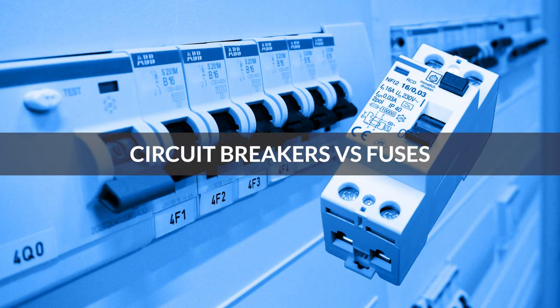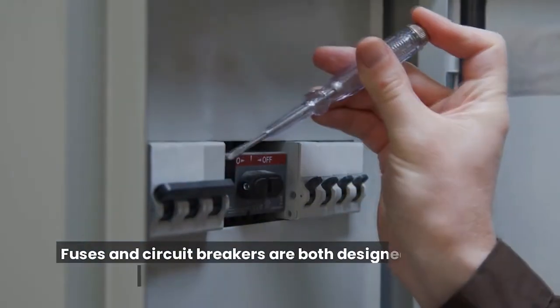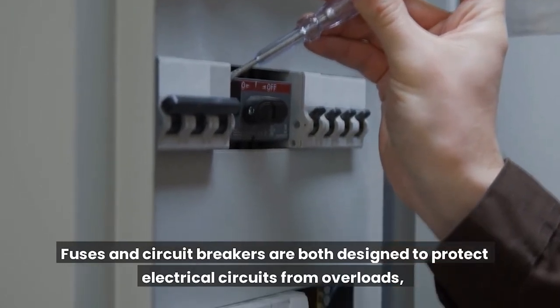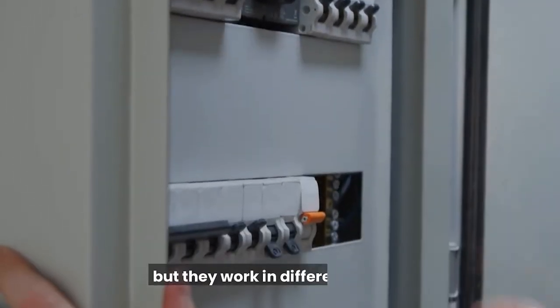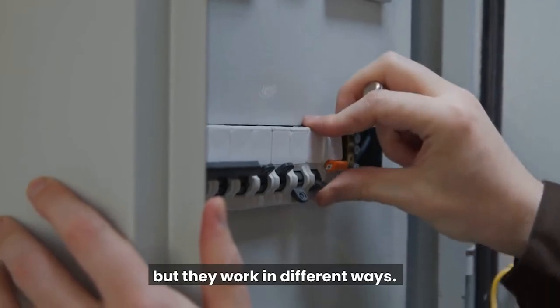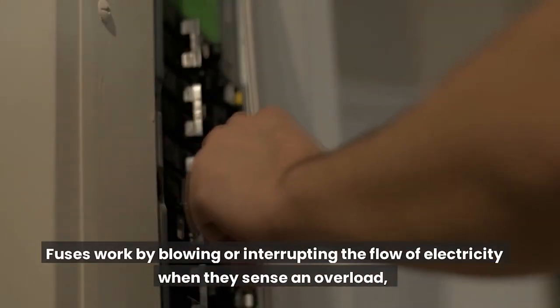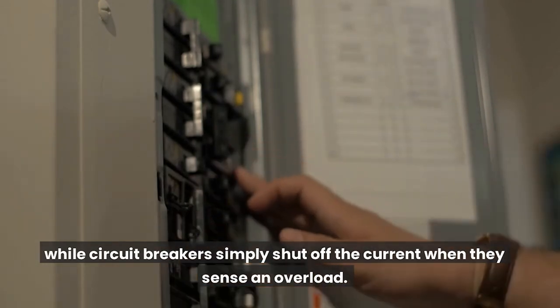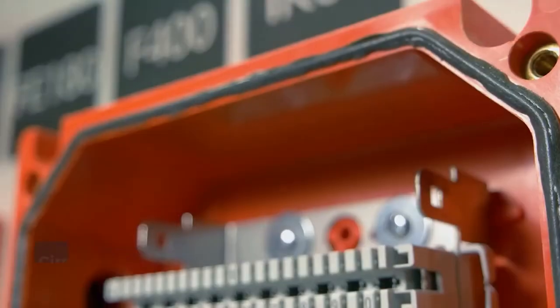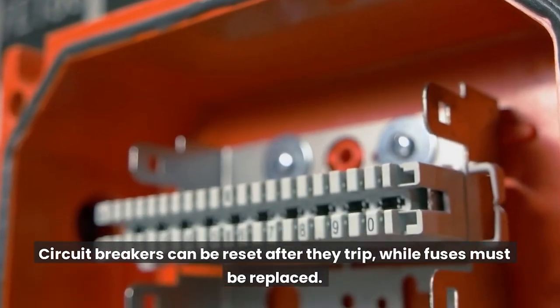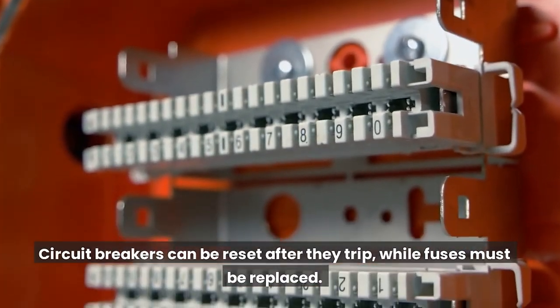Circuit breakers versus fuses. Fuses and circuit breakers are both designed to protect electrical circuits from overloads, but they work in different ways. Fuses work by blowing or interrupting the flow of electricity when they sense an overload, while circuit breakers simply shut off the current when they sense an overload. Circuit breakers can be reset after they trip, while fuses must be replaced.